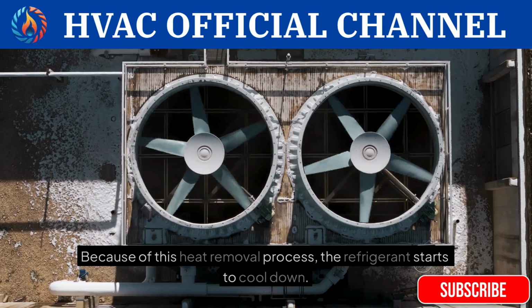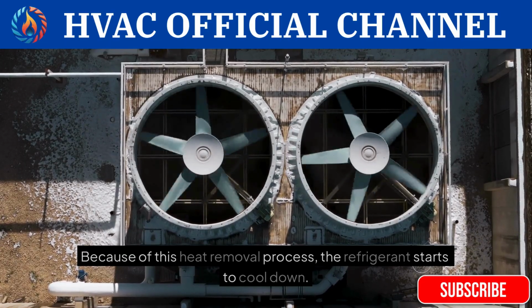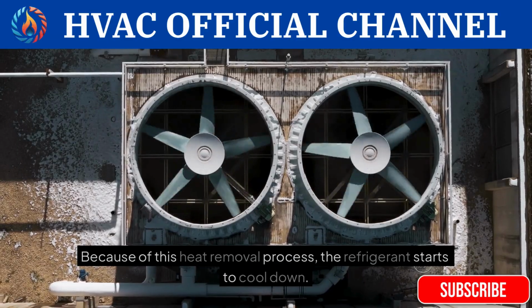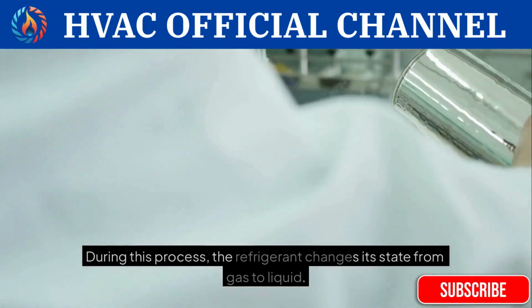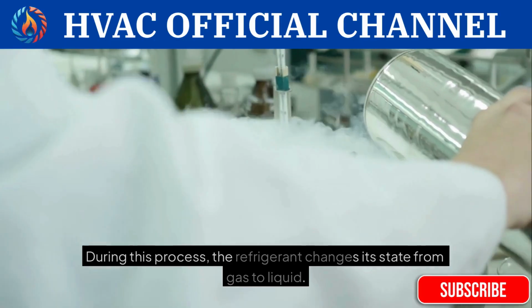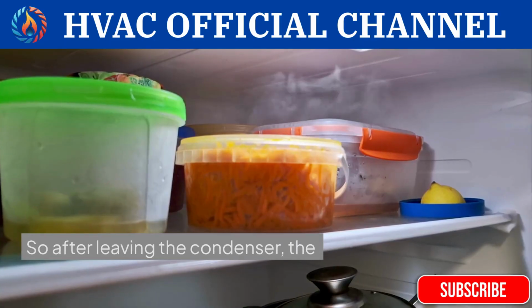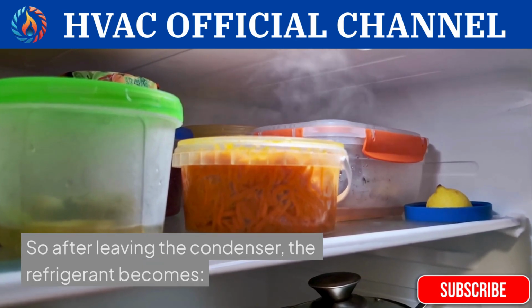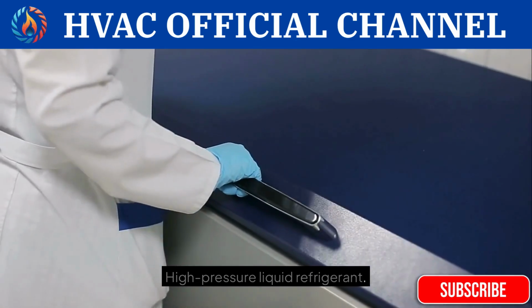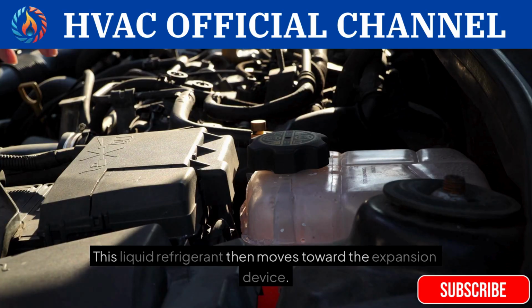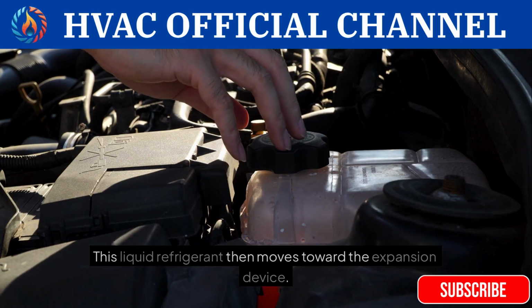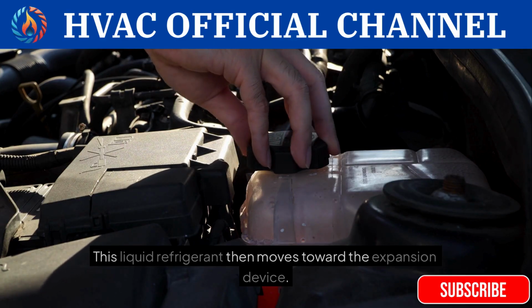Because of this heat removal process, the refrigerant starts to cool down. During this process, the refrigerant changes its state from gas to liquid. So after leaving the condenser, the refrigerant becomes high-pressure liquid refrigerant. This liquid refrigerant then moves toward the expansion device.